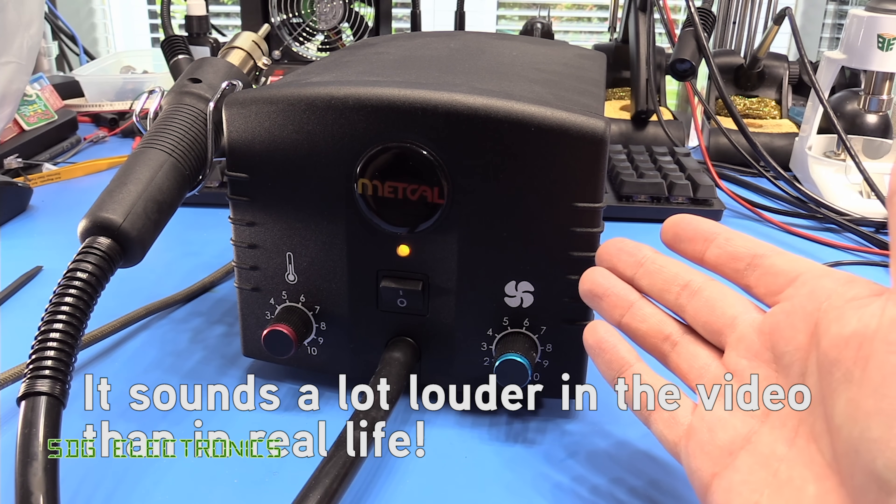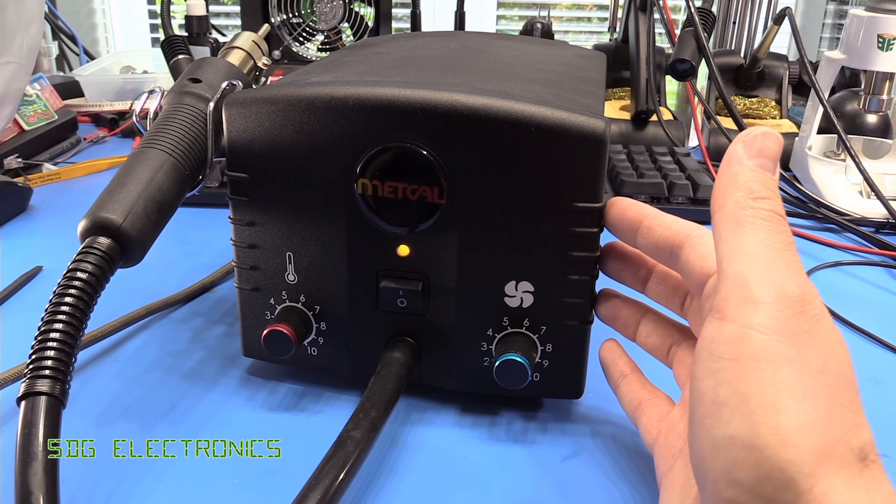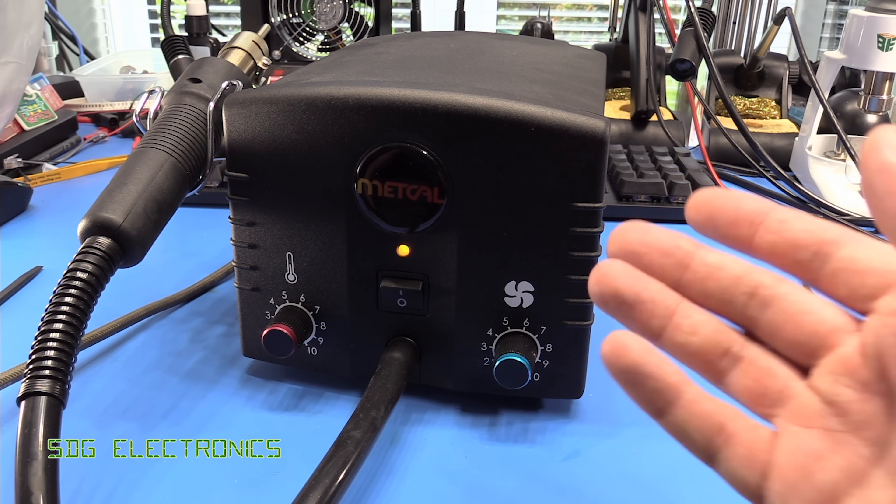So one thing you might not be able to pick up on the video is just how quiet this unit is. Literally, all you can hear is the airflow along with a small mains frequency hum because that diaphragm pump is running at 50 hertz. But really very inoffensive and not loud at all. Not like the Best where you can hear the PWM frequency of the brushless motor that's driving the airflow through the handpiece.